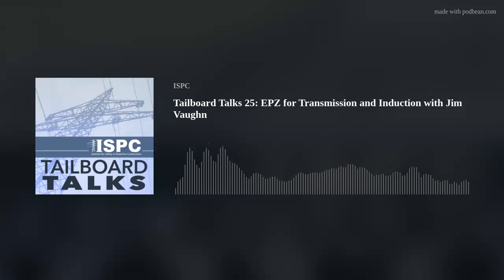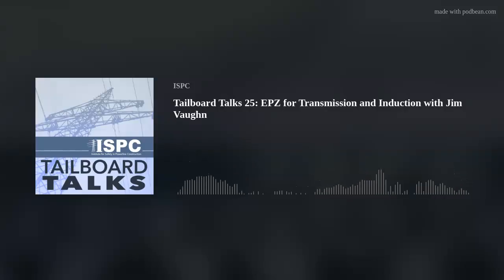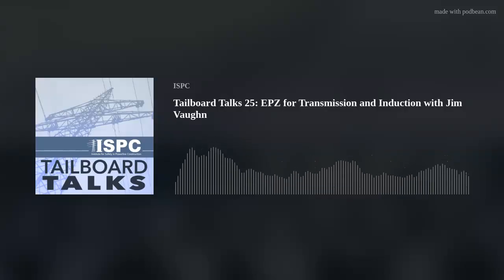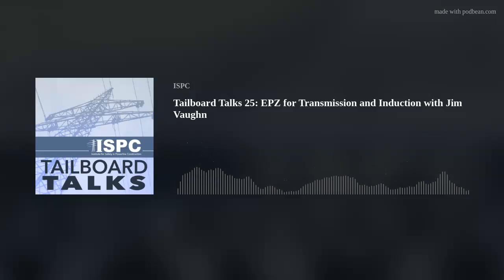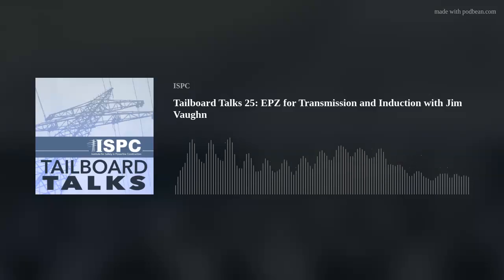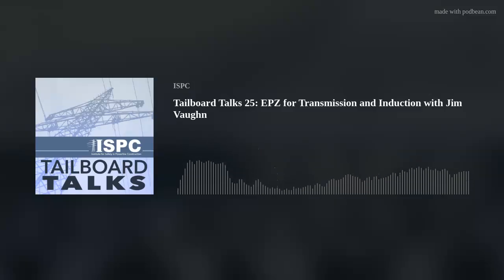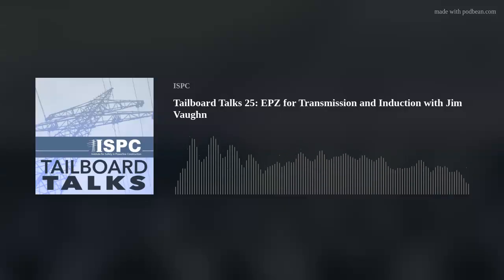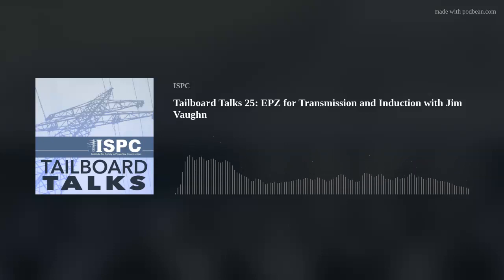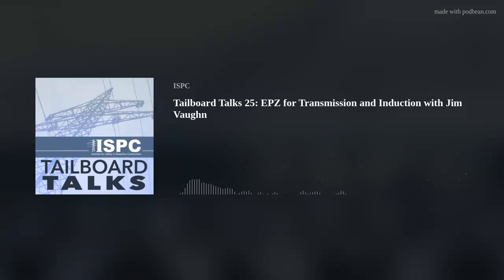grounding to help protect that crew from the event or exposure of induction. So this applies to substations, underground conductors, existing de-energized systems that may be parallel to or near an existing high voltage transmission circuit, and it also applies to transmission circuits themselves. So it's not just about stringing conductors. Wherever induction exists, we have to treat it as if it's deadly unless we can prove it's not.